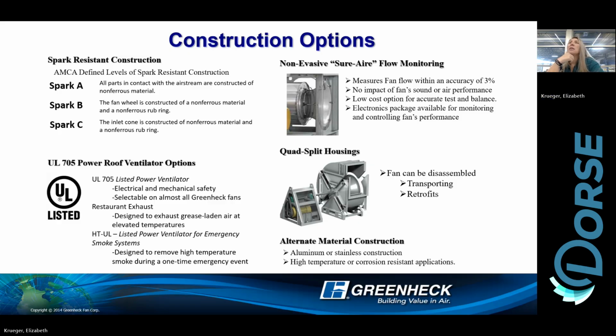Thinking about some other applications as far as the smoke exhaust goes, I did come across one. This was in Nevada, and we had some pretty large USFs on the roof there that were meant for emergency smoke exhaust for a Celine Dion concert. So very interesting. They went through and had to do a check on this and make sure all the fans could actually exhaust the amount of CFM.